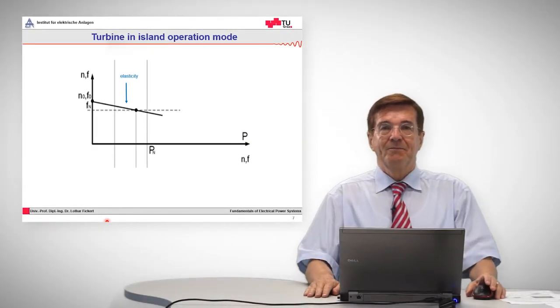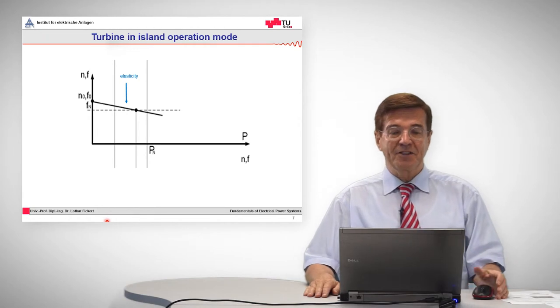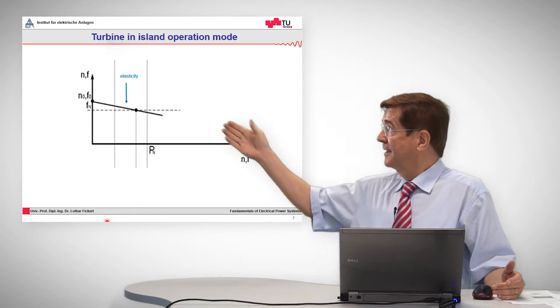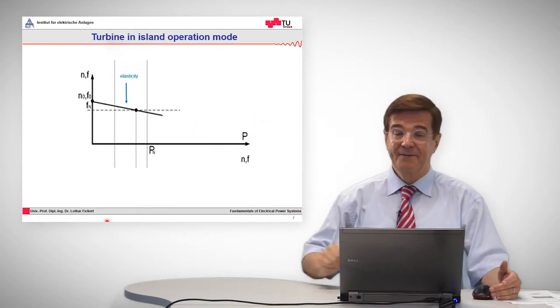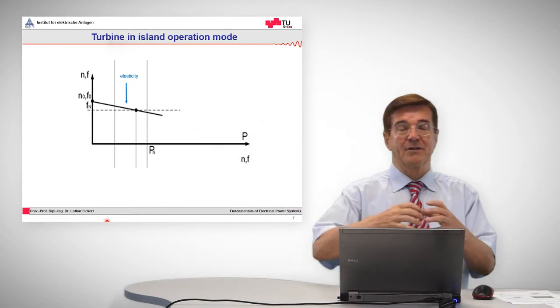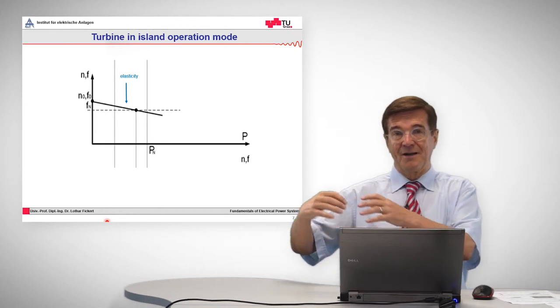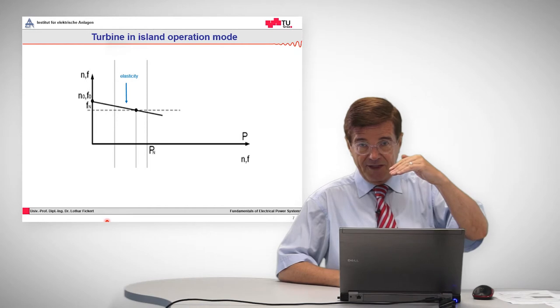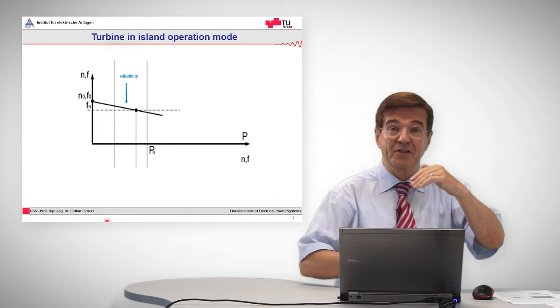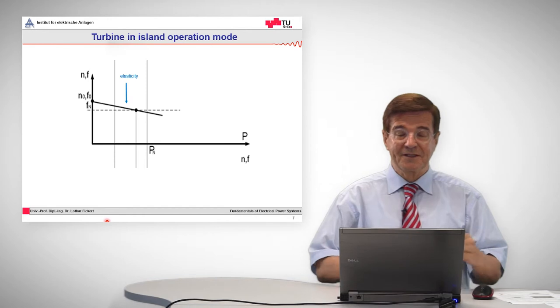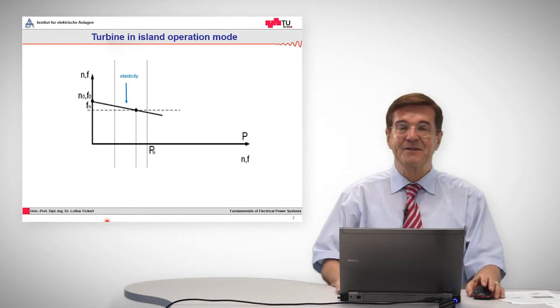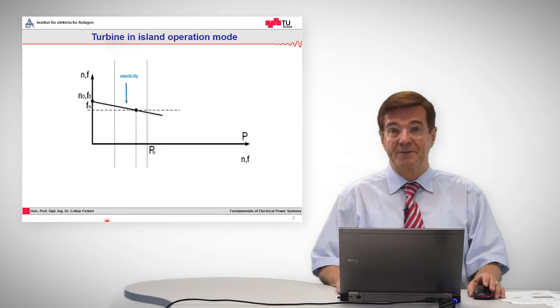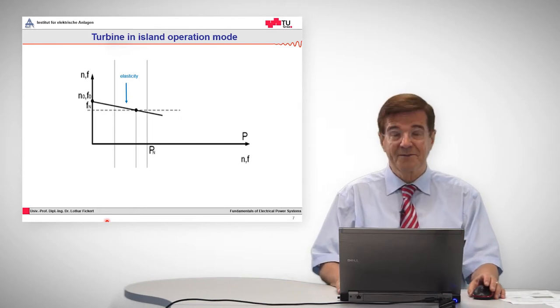The whole process can be shown by a simple diagram, which is called the frequency versus power diagram, which we can see here in this slide. That means when the power demand in such a system goes up, increases, comes to the right side, then the frequency will go down. And that means the power conversion from the primary process will be stepped up in order to keep the frequency stable. But in any case, there will stay a slight frequency deviation. But the system is stable.